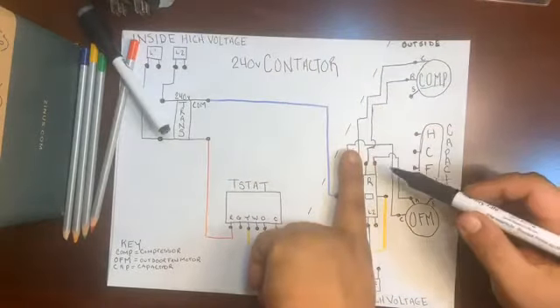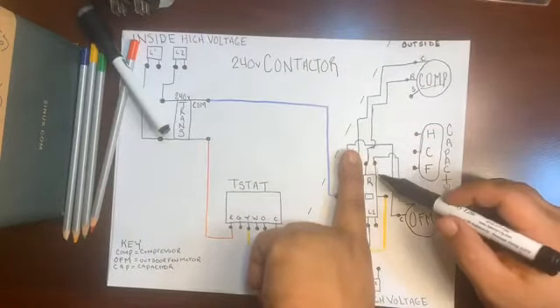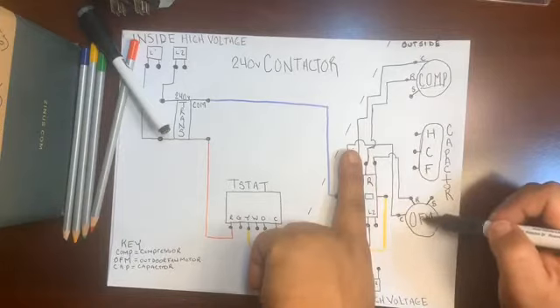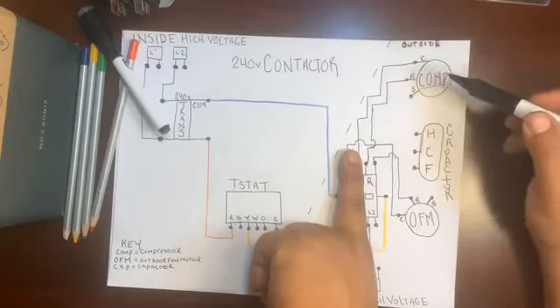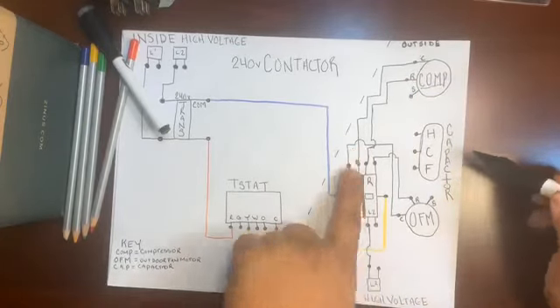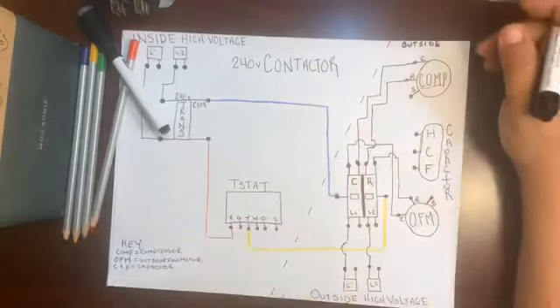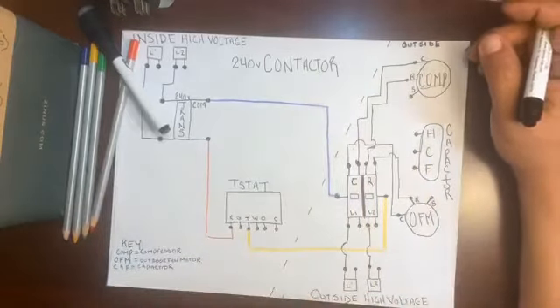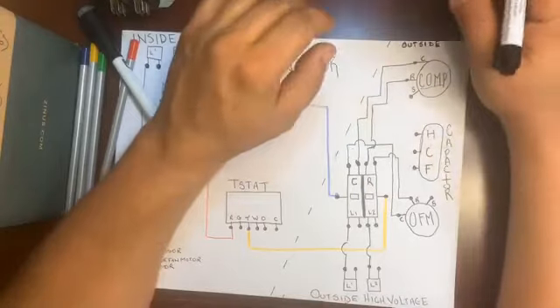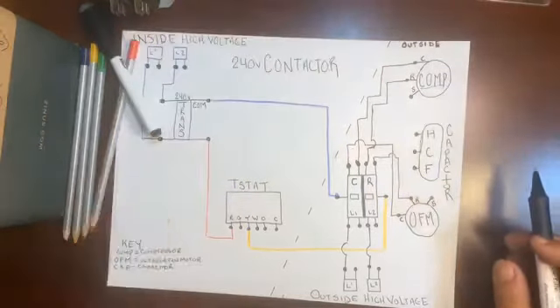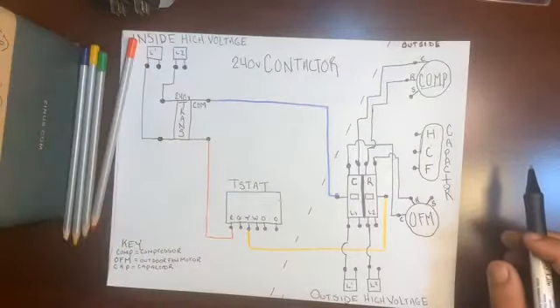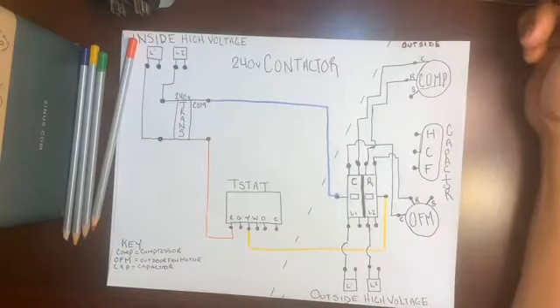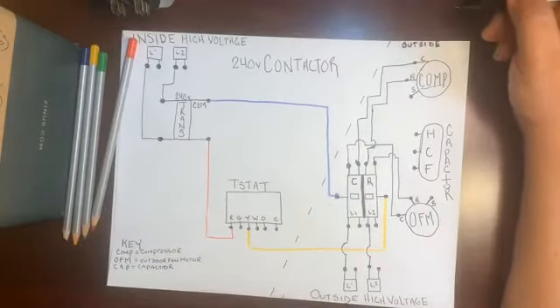So right now we've gotten all of it. We've gotten the outdoor fan motor run and the compressor run. So what's left is our capacitor. We keep seeing these capacitors, and we need to understand how they wire in to every compressor and every outdoor fan motor. Like I said in the very beginning, all this wiring is down to the basic level of every air conditioner. So regardless of the brand, if you're working in a residential system, you are going to experience exactly this.